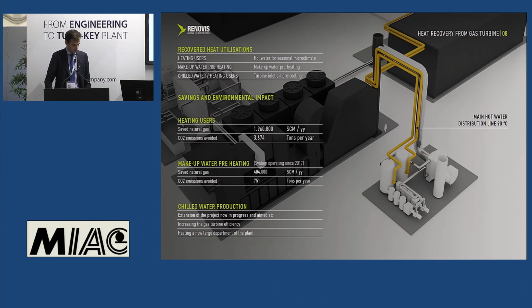As we shall see, part of the hot water produced by the system is used to feed an absorption chiller, and its installation, which is currently in the completion phase, represents the second phase of this project. Thanks to the chilled water produced by the absorption chiller, we are able to optimize the efficiency of the gas turbine.